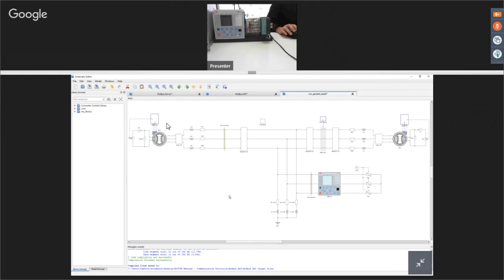So the HIL Connect has high voltage and high current outputs, high current ranging from -10 to 10 amps, and high voltage ranging from 180 to -180 volts, and are connected to the relay, and also the LAN cable is connected to the relay that communicates with GOOSE. So if you load the simulation, we can demonstrate this functionality.